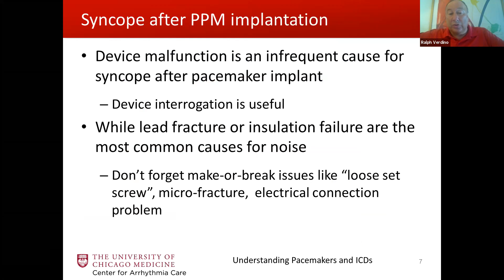So a specific number doesn't rule in or rule out a fracture or an insulation failure. Again, usually they can be way high or way low, but it can point that something may be wrong or heading in the wrong direction. So you like your impedances to be stable regardless of where they are. And if you're implanting a device, it's nice to have a relatively high impedance, because you'll use a bit less energy, a bit less battery, by pacing with higher impedances. Great point, Ralph.